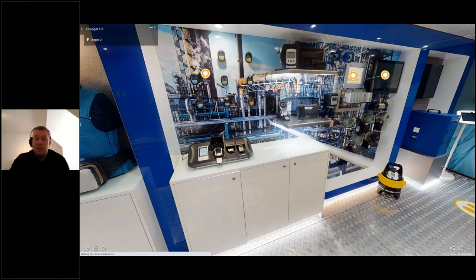It's critical to know that all of your detectors are working or will respond in a gas event, and that's where the X-Dock comes in, right down here. This is our automated bump testing and calibration station. It's easy to use, it's fast — you can bump test in just 8 to 15 seconds, and it supports multiple gas inlets. It's fully modular, and you can test or calibrate up to 10 detectors at the same time in multiple configurations. So it's incredibly flexible and compatible with all of the detectors we've looked at so far.